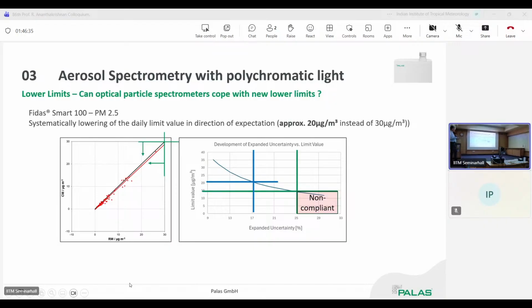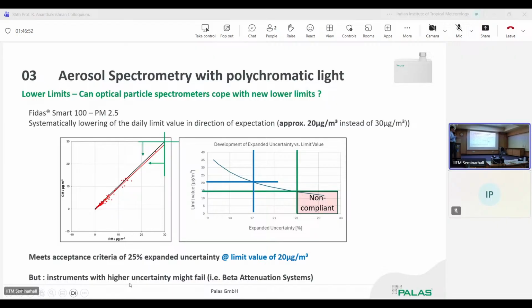Europe reduces to 20 micrograms, meaning minus 10, we are still at an uncertainty better than 25%. So we slip, of course, yes, we do. That's normal, but we are still at plus minus 25%. With other systems, and this we also know, if you have initially higher uncertainties, especially for regulatory elements, then it can happen that you are out of that plus minus 25% area, and then you're not compliant anymore. So for us, we see that it's perfect. Those systems can be used also for regulatory measurement and also fit the new standards which will come in the future.